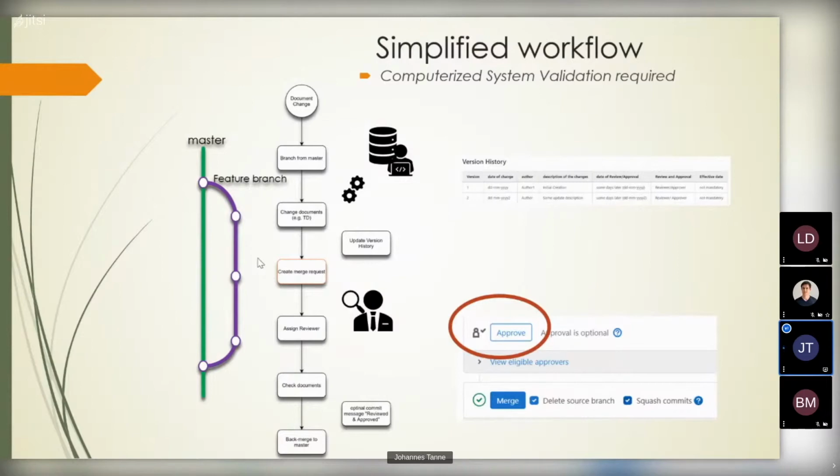Let's take the technical file repository as the master. Then you change everything related to your software change in the respective documents, let's say the software specification and the software architecture. Then you change the version history. You see it here on the right.